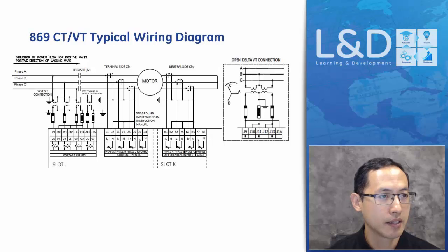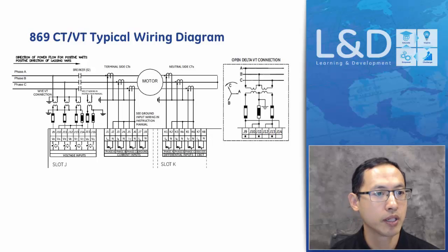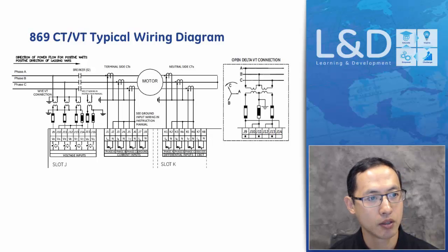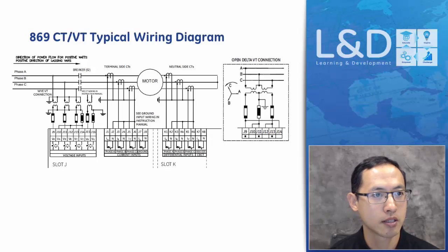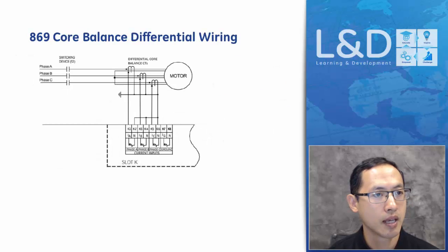For the 869 connections, this typical wiring has a differential relay configured, and this is the internal summation method. So it's using 2 slots, J and K slot, with 1 connector for the terminal CTs and another connector for the neutral side CTs. And there's another way for the differential. It's just like the traditional SR relays for 469. It's a core balance differential wiring. So it's using core balance CTs to connect to 1 input of the K card.